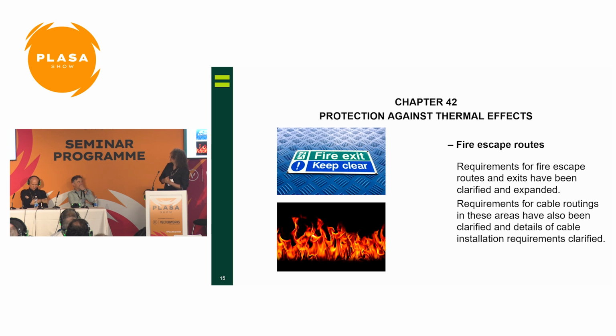This one on the screen is protection against thermal effects - this is about fire escapes. It might be, for instance, in a building like this, or you might be out at an event, and you've got to get cables from a truck outside into the building, bringing them through areas that might be escape routes. So it's a discussion with the building owner, whoever's given you the work, to establish what are escape routes and what you need to do in that area.